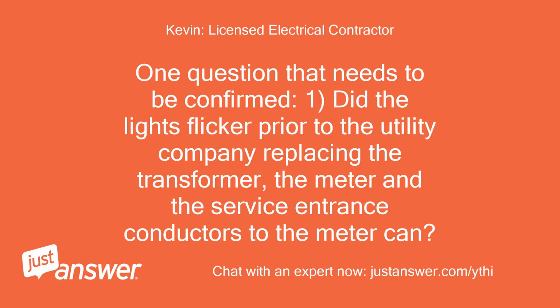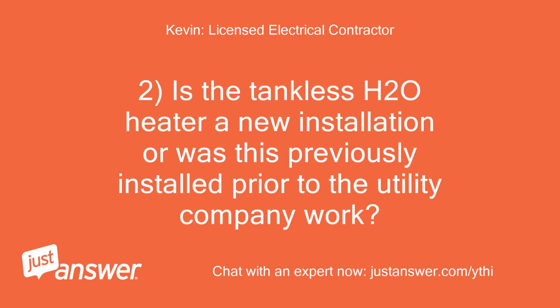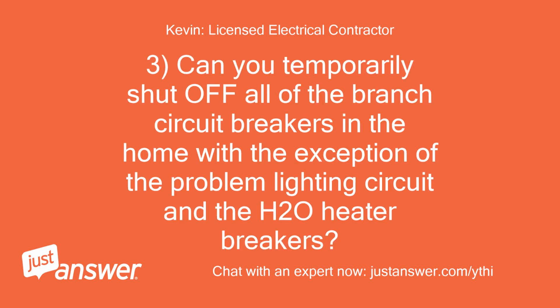One question that needs to be confirmed. 1. Did the lights flicker prior to the utility company replacing the transformer, the meter and the service entrance conductors to the meter can? 2. Is the tankless H2O heater a new installation, or was this previously installed prior to the utility company work? 3. Can you temporarily shut off all of the branch circuit breakers in the home with the exception of the problem lighting circuit and the H2O heater breakers?